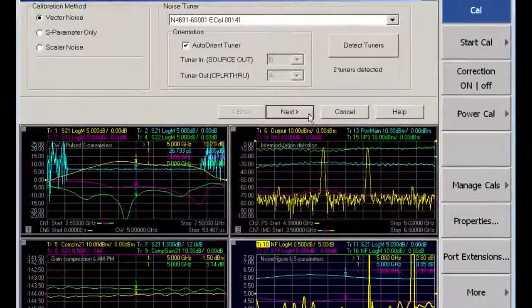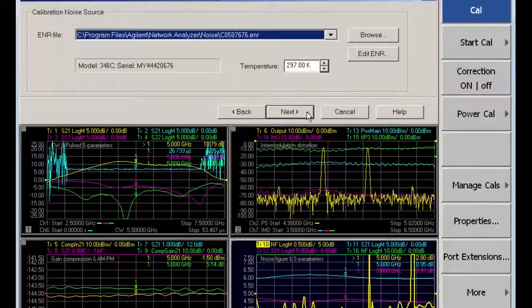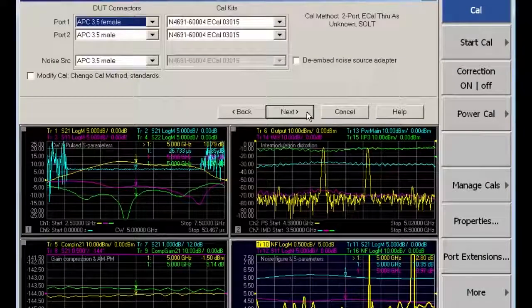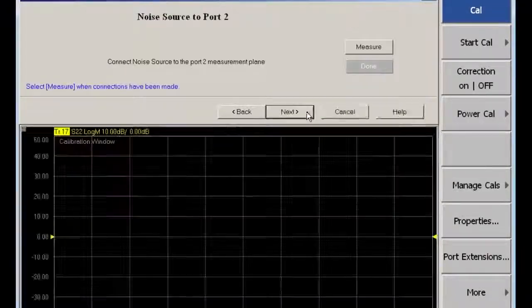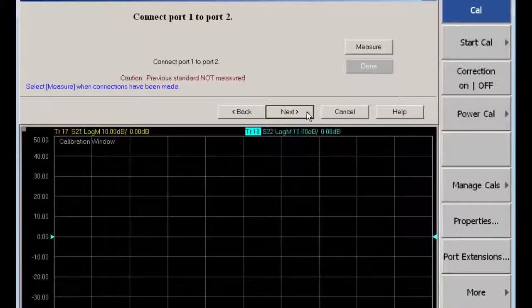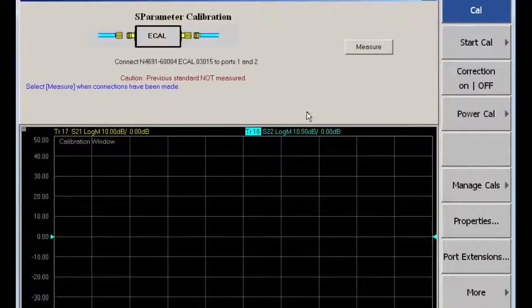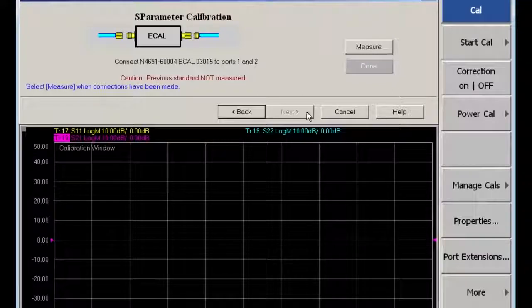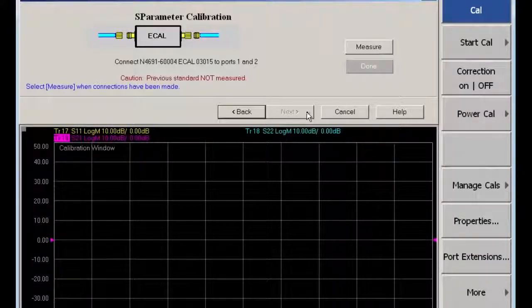Calibration is simple with a calibration wizard that guides the user through all of the required calibration steps. A mechanical calibration kit or an electronic ECAL module is required to calibrate the S-parameter receivers, and a noise source or power meter is required to calibrate the noise receiver.